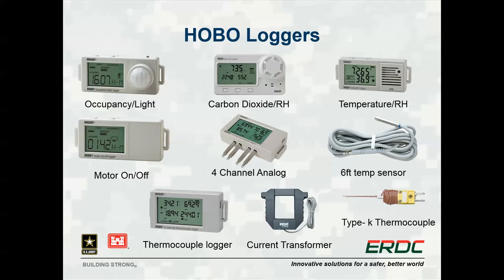Data loggers can serve as the backbone for any energy auditing, commissioning, or retrocommissioning study, and can be used to monitor a building over an extended period of time. Many loggers have digital displays showing real-time measurements, but time series data must be handled using the free associated software, a link to which can be found in the description below. Common studies include determining the cost-effectiveness of lighting controls using occupancy and lighting loggers, tracking carbon dioxide levels to determine if minimum outside air flow can be reduced or tied to a CO2 sensor, testing an economizer to ensure it is functioning properly, and tracking equipment power usage.